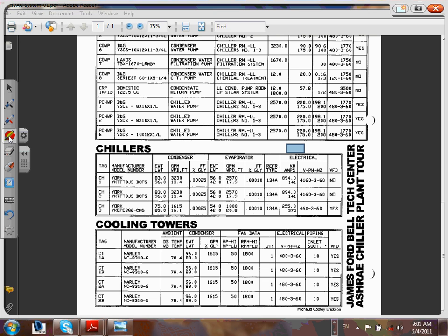So if you guys look at the chillers, here's my chillers. And here's my electrical information. And now I have this amount. Anybody can read it for me here? 894 kW. And look at the voltage. Anybody can see the voltage as 4160. That's medium voltage chillers. 4160. They're using medium voltage chillers, guys.